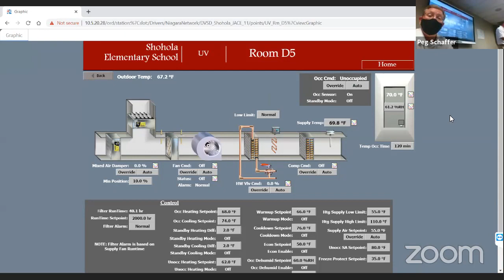Marvin added some dehumidifiers. If you lower the air temperature thinking it'll take care of the humidity, you'll actually get moisture—like on gym floors and things like that, because the air inside and the air coming in are too opposite of one another. By changing the dew point, it was causing us problems. We thought lowering the temperature would solve it, but that wasn't the case, so we changed some programming to try to solve the issue. It worked, I'd say, a little bit—not 100%, but it definitely helped, and adding dehumidifiers improved things. Complaints are way down.